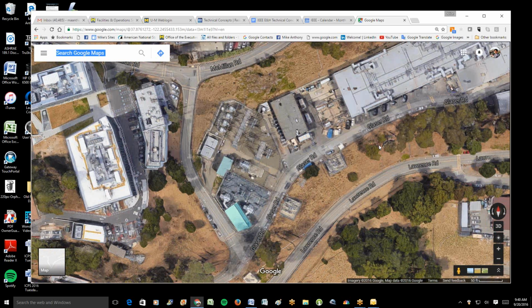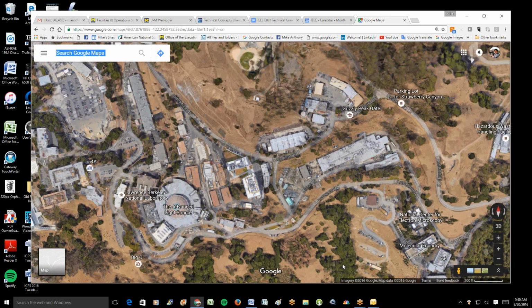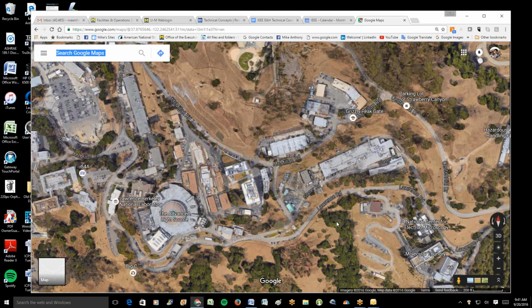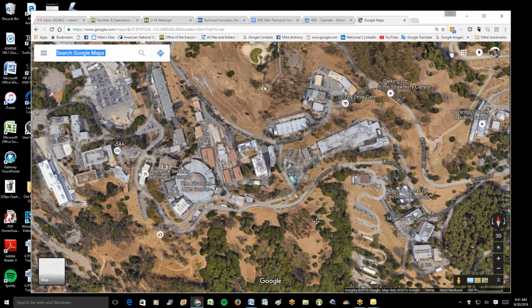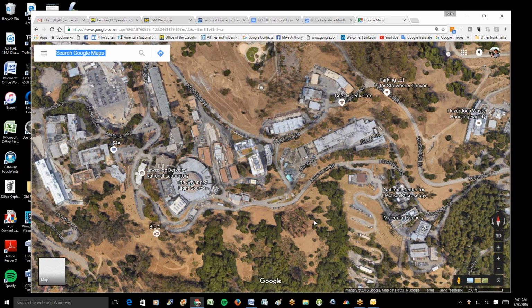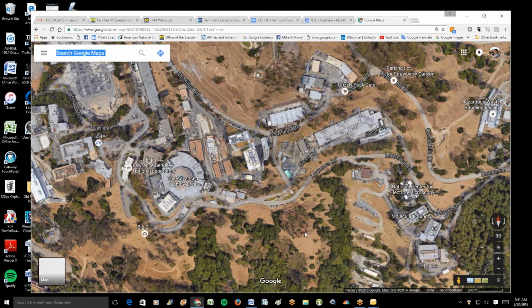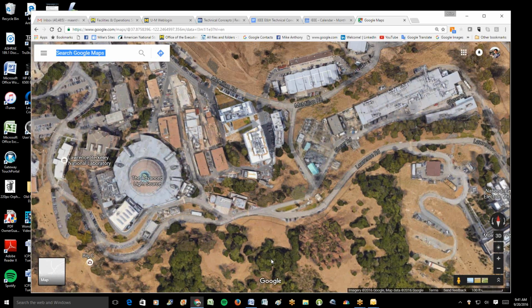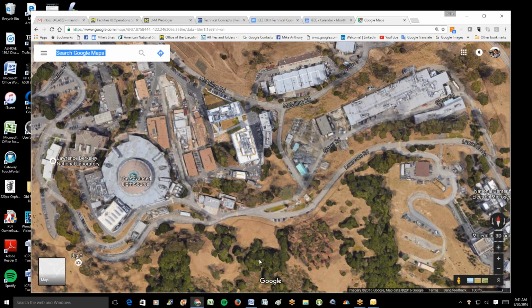That's why we have so much excess capacity built in currently. Because, like I said, we ran 12 megawatts as our typical load on the system at any time on a summer day, which doesn't get too hot in Berkeley. And we had a system that could provide, I think it was 41 megawatts actually. So we didn't care what anybody turned on, or what they ran, or when they ran it. And we don't have a power factor demand issue on our utility bill.